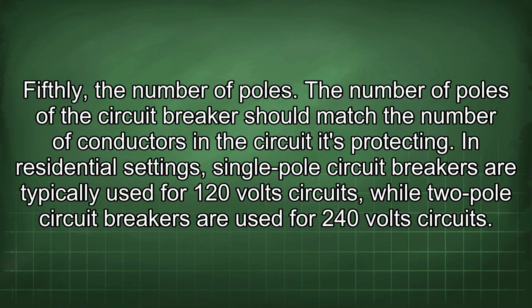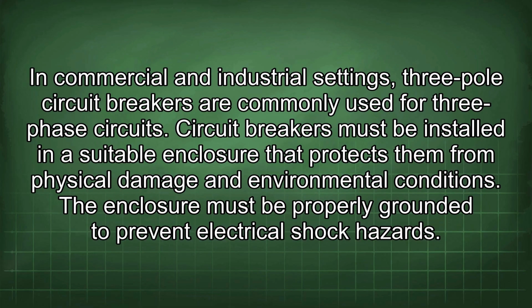Fifthly, the number of poles. The number of poles of the circuit breaker should match the number of conductors in the circuit it's protecting. In residential settings, single-pole circuit breakers are typically used for 120-volt circuits, while two-pole circuit breakers are used for 240-volt circuits. In commercial and industrial settings, three-pole circuit breakers are commonly used for three-phase circuits.